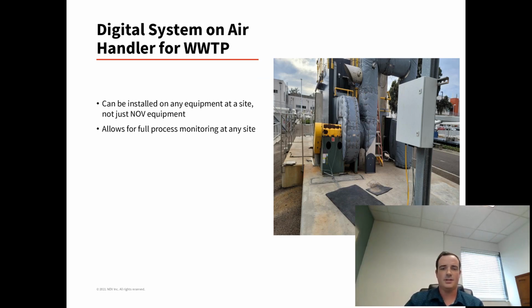And lastly, I want to mention that these systems can be installed on really any type of rotating equipment and in any type of environment. Here you see an example of installing this on an air handler. There was a problem unit for the customer. They were having multiple bearing failures, and what this allowed us to do was monitor bearing temperature and vibration at the bearings and tell them if they were having any failures.